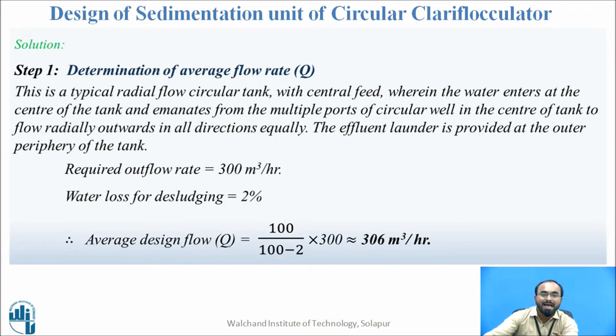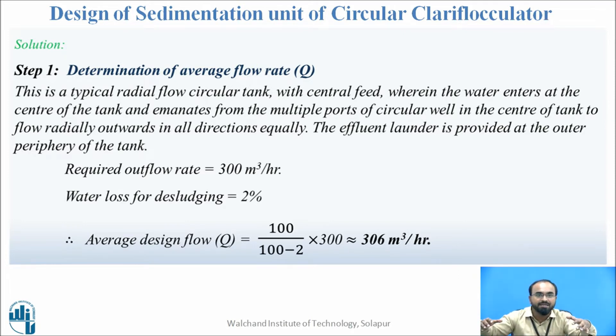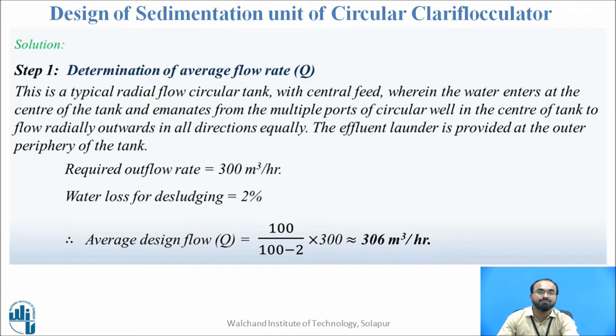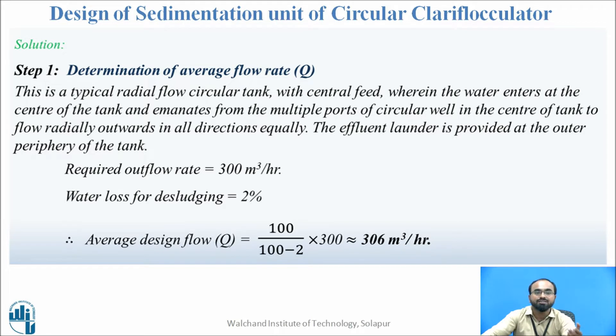We assume water from the flocculation unit spreads to the sedimentation unit through multiple ports. Since 2 percent of the flow is used for desludging, we need to add that 2 percent to the sedimentation unit flow. The average design flow rate is: Q = (100 / (100 − 2)) × 300 = 306 meter cube per hour.